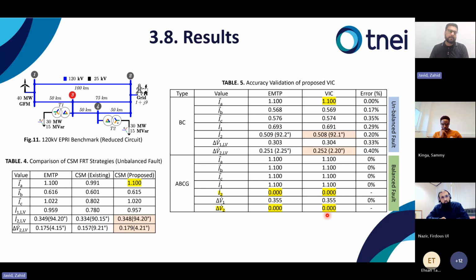So here are some results. This is the EPRI reduced benchmark. Here we put a fault on bus 3. This is a comparison of the current saturation FRT strategy with the existing method. We can see that with the proposed method, it hits the limit of 1.1 pu. And if we look at the angle difference between the negative sequence voltage and current, it is almost 90 degrees, but with the existing method, it is less than 90 degrees. So it strictly complies with the IEEE standard.